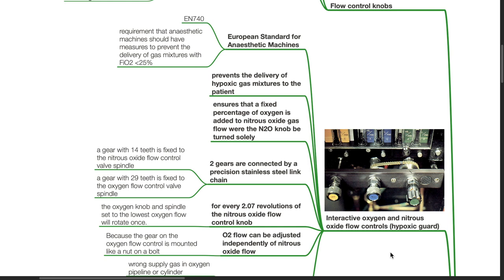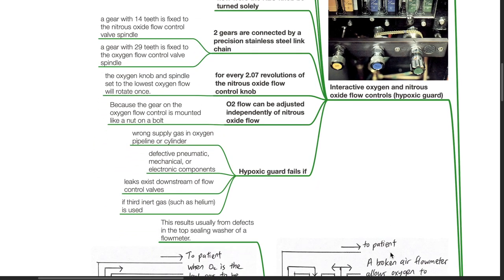Oxygen flow can be adjusted independently of nitrous oxide flow because the gear on the oxygen flow control is mounted like a nut on a bolt. The hypoxic guard fails if wrong supply gas in oxygen pipeline or cylinder occurs, defective pneumatic, mechanical or electronic components occur, leaks exist downstream of the flow control valve, and if a third inert gas such as helium is used.